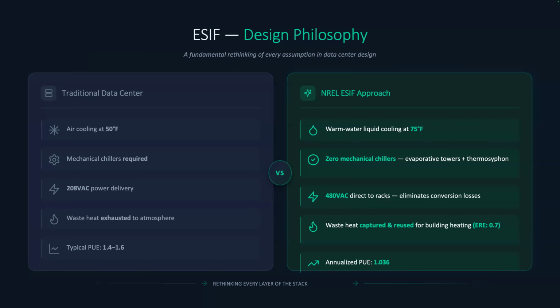They also paid a lot more attention to some of the electrical distribution systems in that era, around 2010. 208 volt was very typical; these are now 480 volt. Our ESIF dictated to vendors that they wanted 480 volt AC direct to the rack, eliminating a bunch of transformation steps.